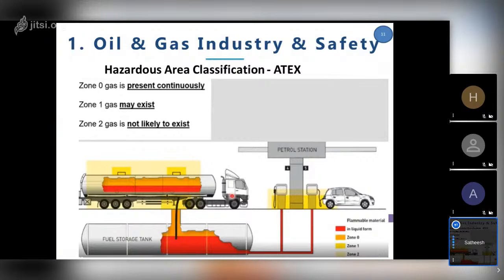You're very close to the danger. So to make it clear, zone 0 is this area where gas is present continuously. Recall the fire triangle: fuel is present, oxygen is there, so only heat is needed. Heat can be a spark, a dissipation, or a lighter. Whatever it is, it can create an explosion.